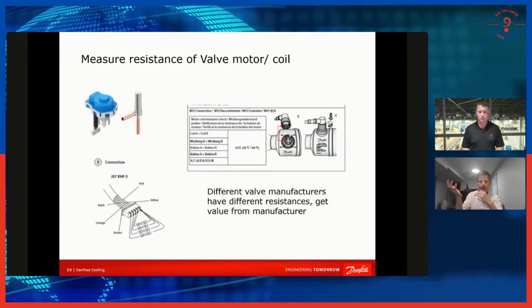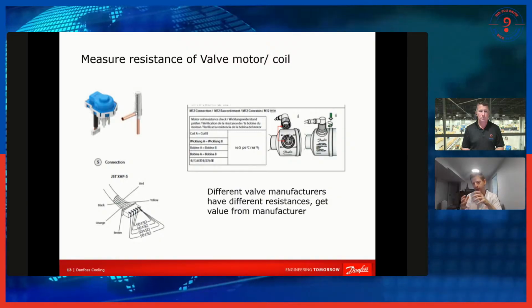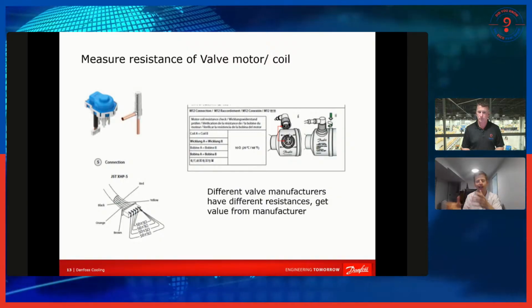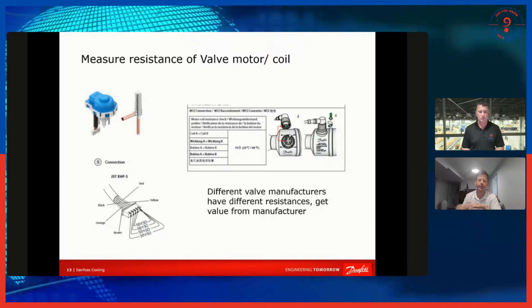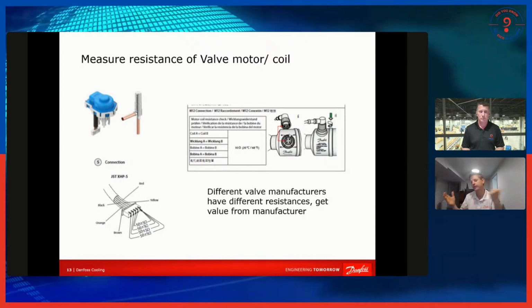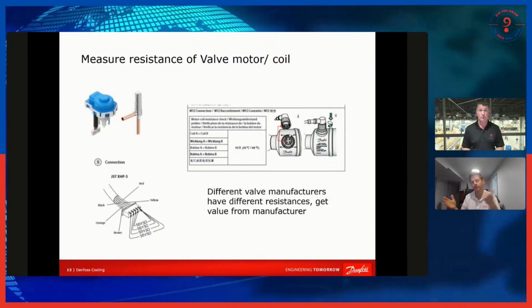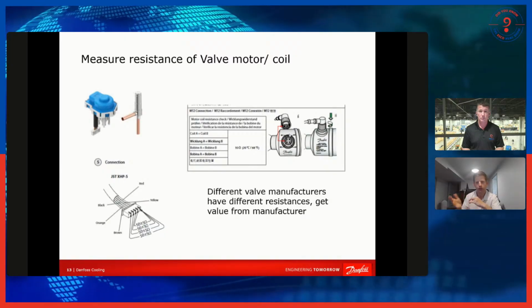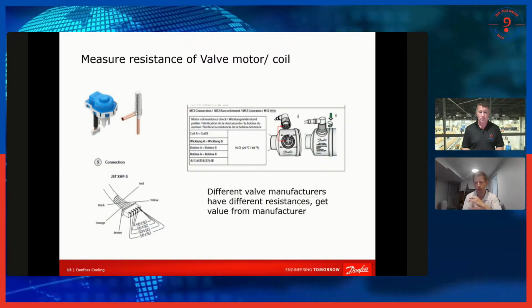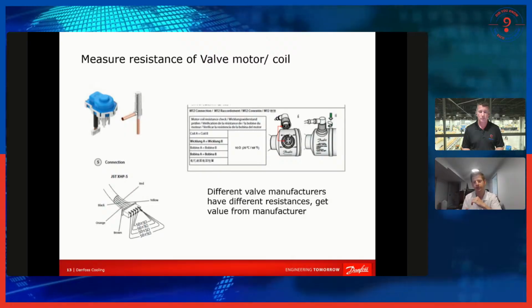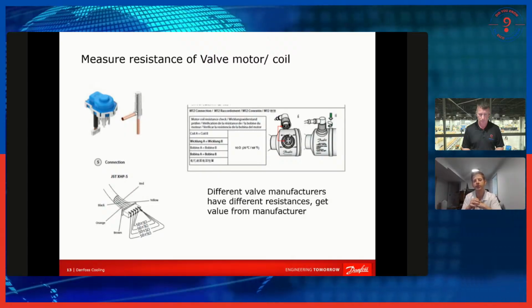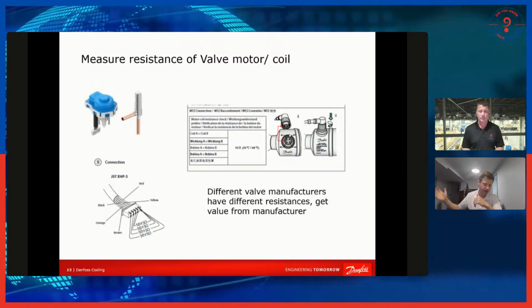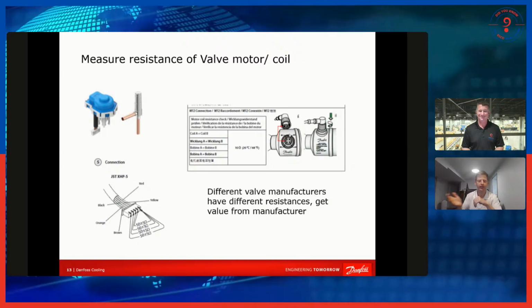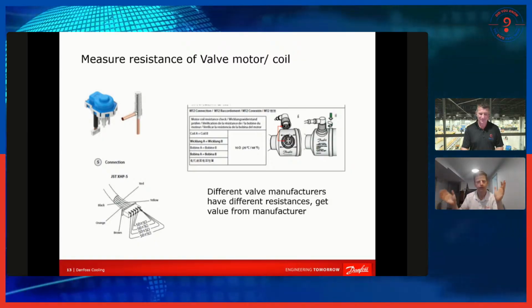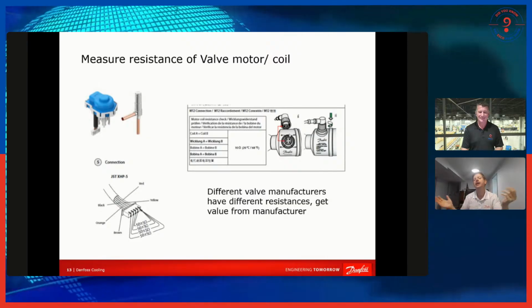The controller tells the EXV to move, and the controller just has to assume the EXV did what it was told. If one of the poles inside of the motor is burned out, then it's not going to do what it's told. You might have a controller that thinks the valve is 100% open because it told it to go 100% open, but it's lost steps because one of the poles is burned out, so it's not able to do the number of turns it's supposed to. The controller thinks it's 100% open, but in reality the valve is 30% open or whatever the number is. And that might be how you get your alarm.